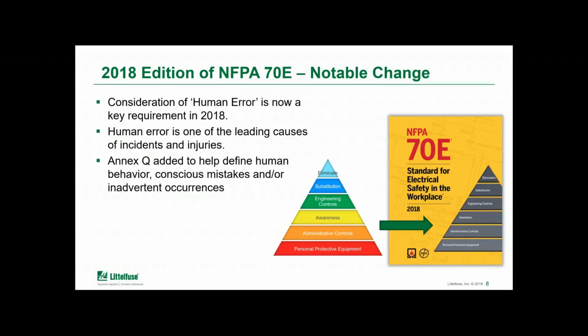Now, one of the other themes in the updated document is that there's been consideration given for potential human error. And those errors can be conscious mistakes, for example, somebody who deliberately ignores a PPE requirement because they're in a rush, there's something they need to do that will just take a second, or accidents, where someone may have dropped a wrench, is the classic example, an unintentional mistake that can occur. So given that human error is one of the leading causes of electrical incidents, the inclusion of the hierarchy of controls really directs users to evaluate the options they have on the upper half of the hierarchy. And if you can focus on those, it really reduces the impact of human error on safety, just because the items at the bottom of the pyramid are subject a little more so to human error.